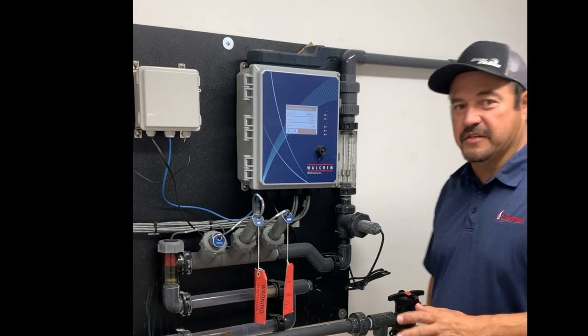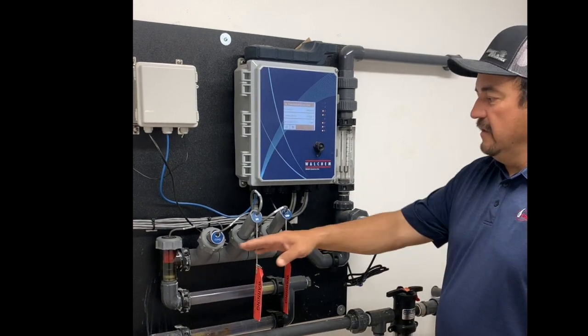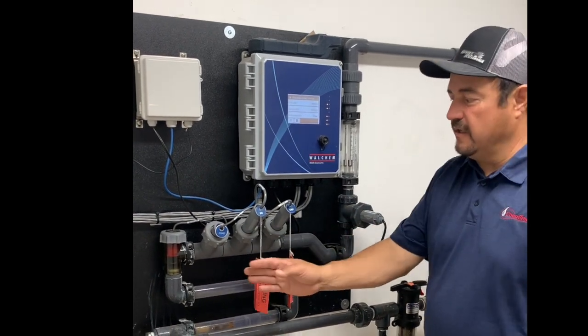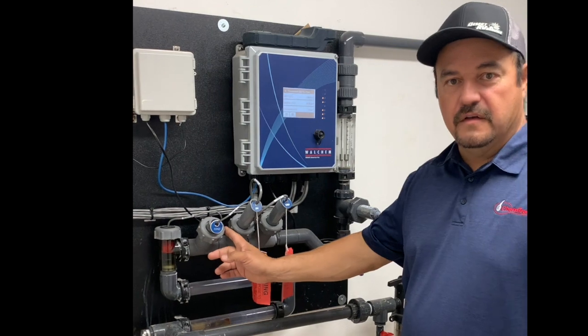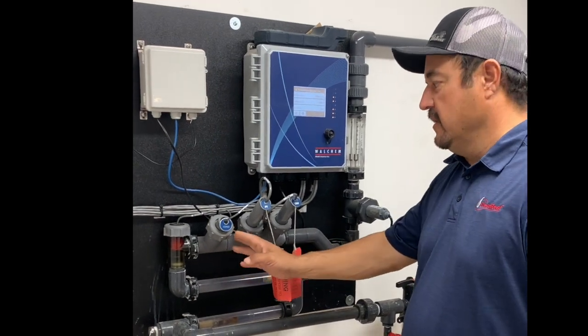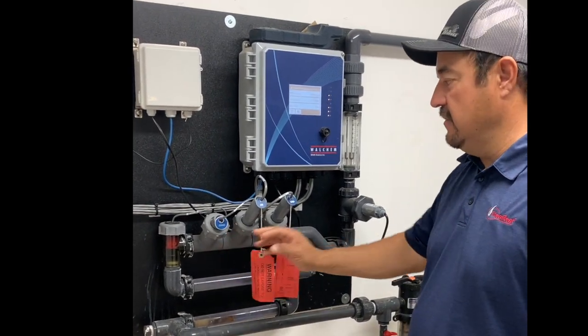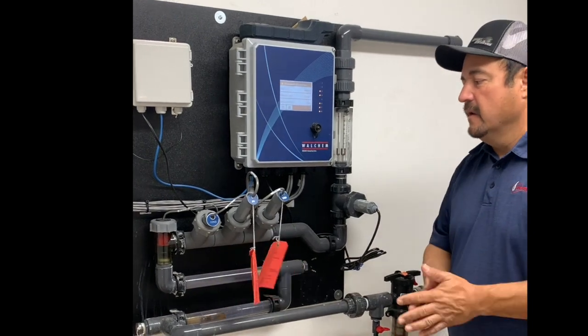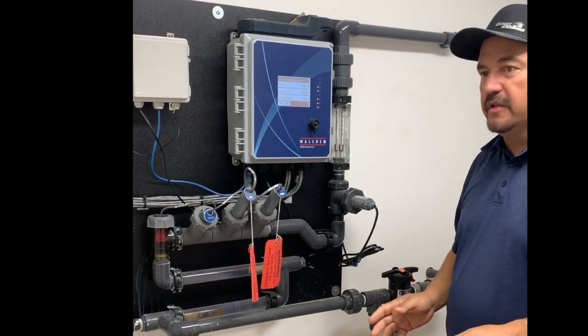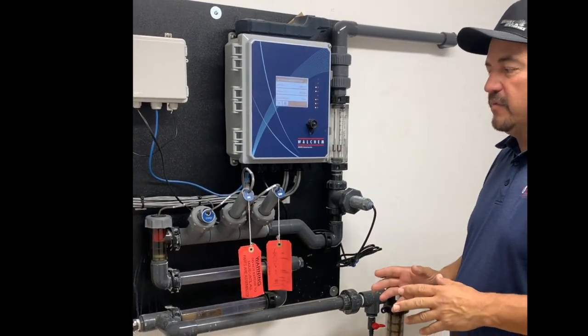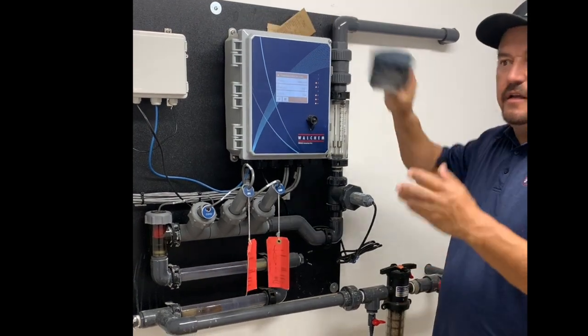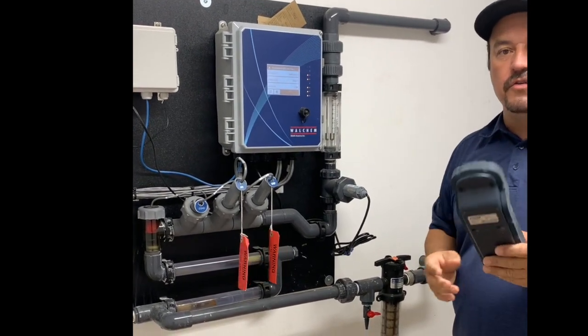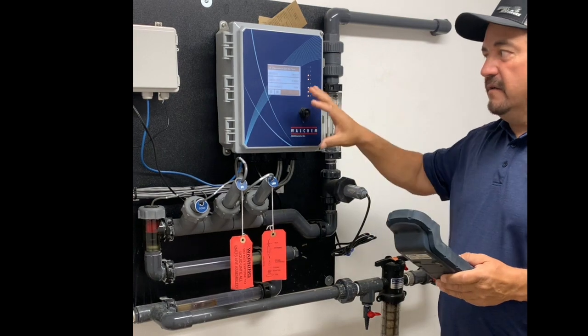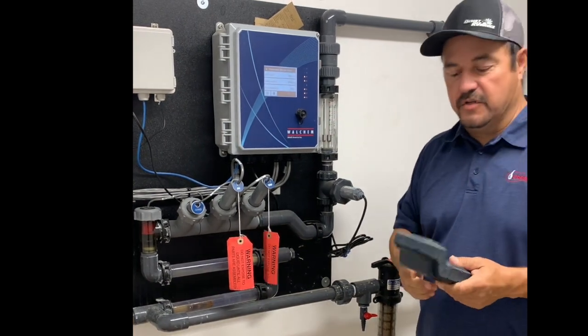We're going to do a process calibration on one of our sensors. In this particular case, we're going to do a conductivity process calibration. It would be the same idea as conductivity, pH, or ORP.